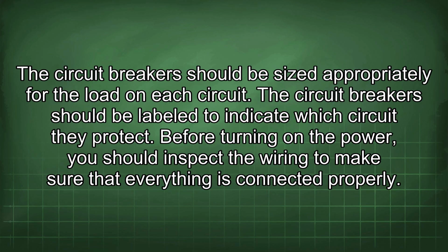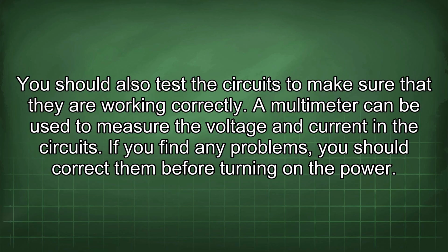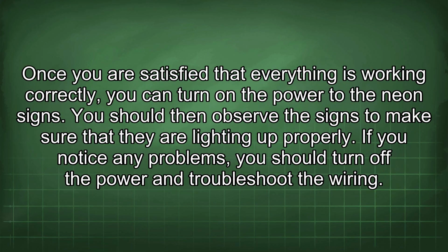Before turning on the power, you should inspect the wiring to make sure that everything is connected properly. You should also test the circuits to make sure that they are working correctly. A multimeter can be used to measure the voltage and current in the circuits. If you find any problems, you should correct them before turning on the power. Once you are satisfied that everything is working correctly, you can turn on the power to the neon signs. You should then observe the signs to make sure that they are lighting up properly. If you notice any problems, you should turn off the power and troubleshoot the wiring.